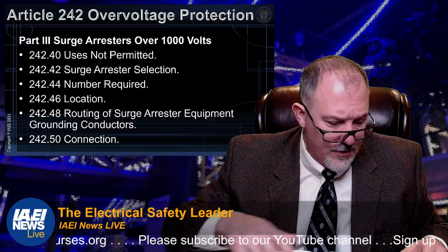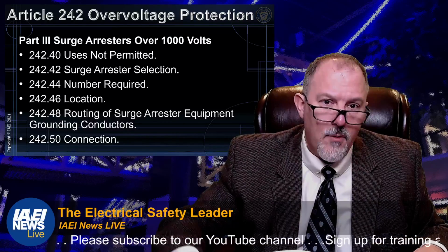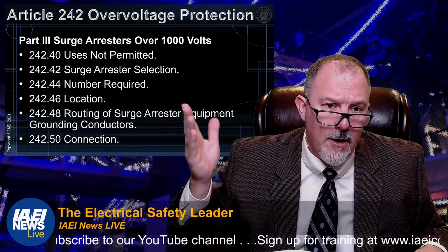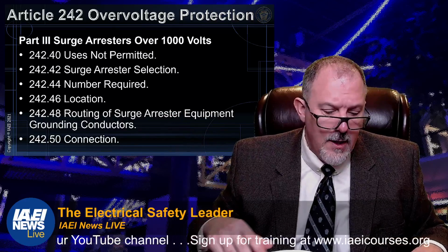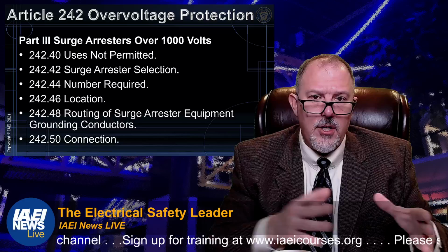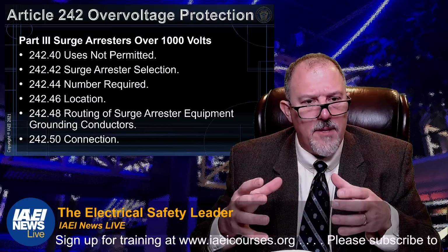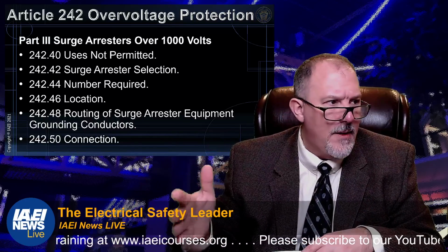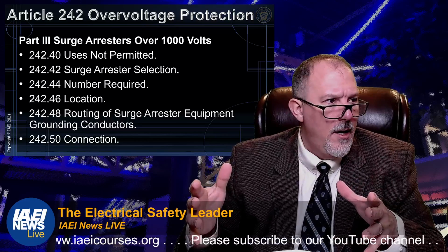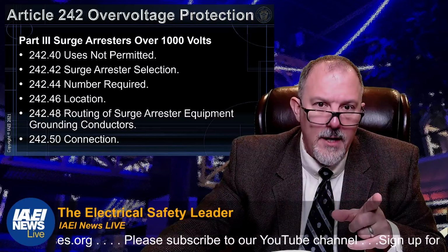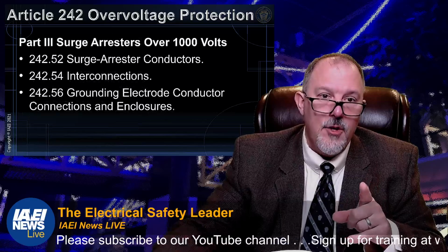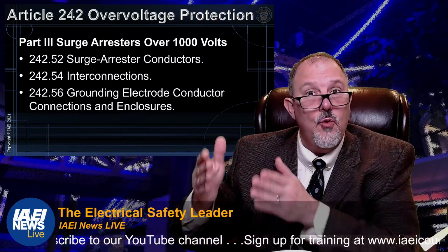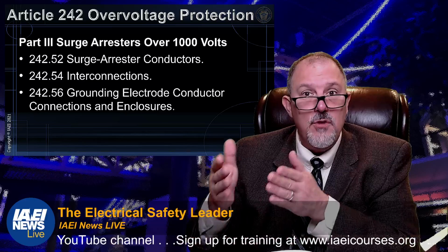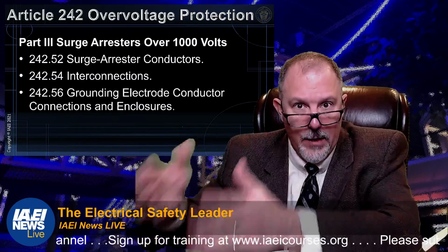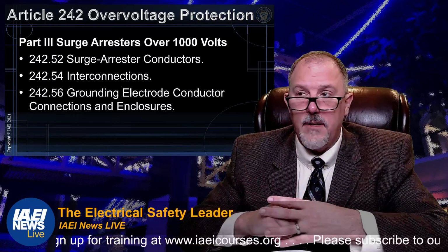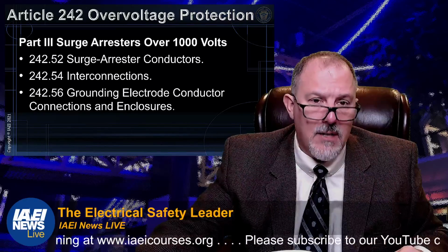Now you're over 1,000 volts. Where you're not permitted, the surge arrester selection, the number required, location, routing, and connection. So this 242 pulled together all of the other requirements that you find in other locations within the National Electrical Code and put them into one spot. But again, you're still going to have to go to 700 to tell you when you need to install it, 230, when you need to install it, 708, when you need to install it, in other areas that we already talked about.